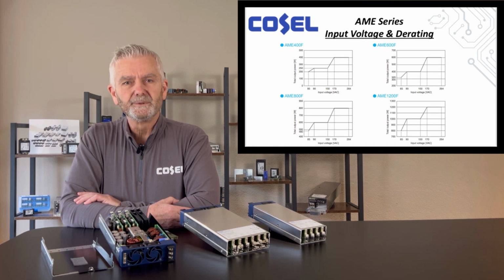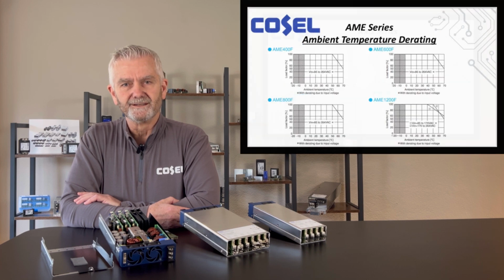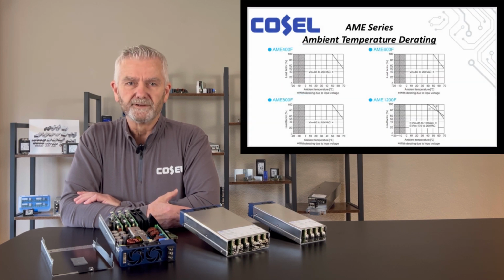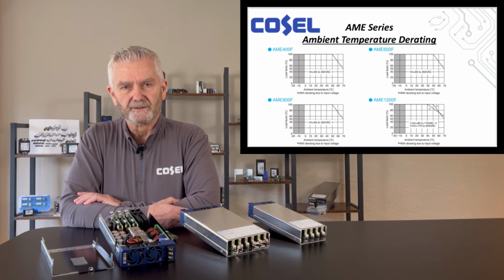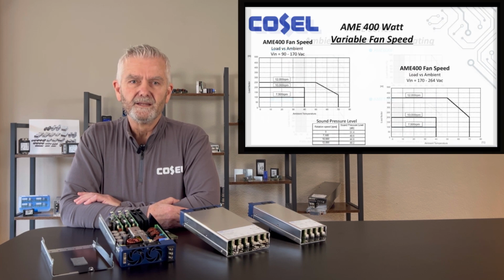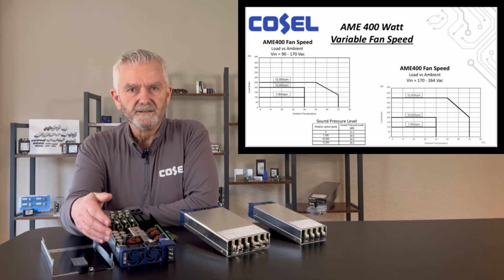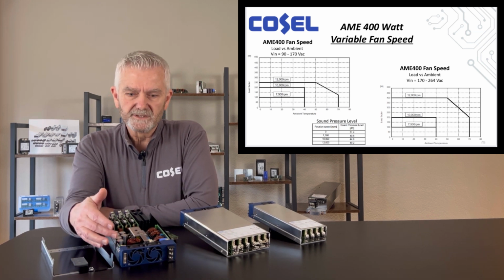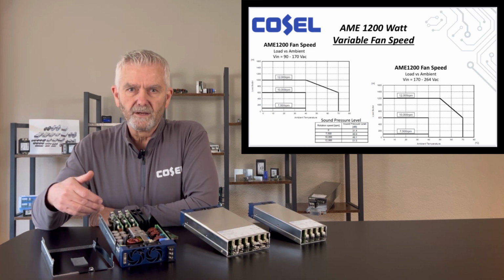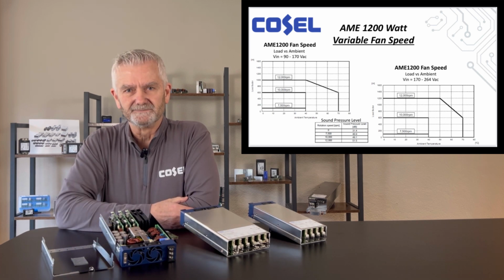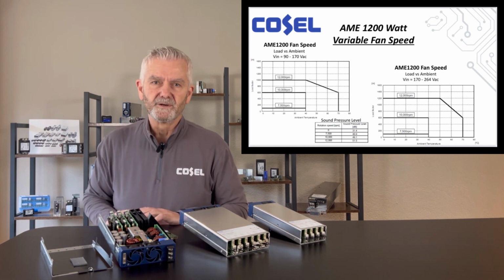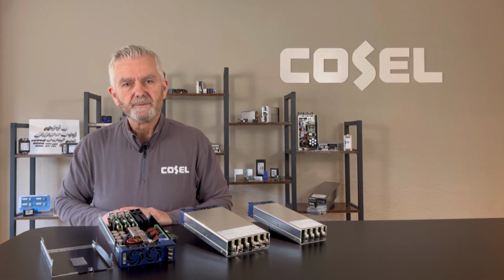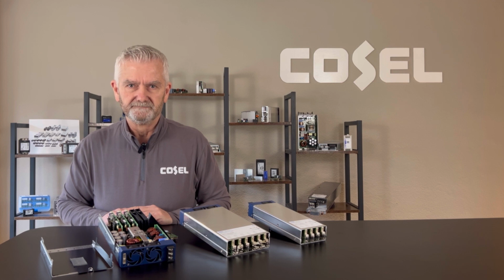Hold-up time is typically in the 16 to 20 millisecond range for 80% to 100% of the rated load. All variations of the AME series are rated for full power at 50 C ambient and derate to 50% of the rated power at 70 C ambient. The front ends have variable speed fans that adjust as indicated in the charts with standard airflow from front to back, with back to front available as an option. A 5 volt at 1 amp auxiliary output is standard, with an option for a 12 volt auxiliary output.